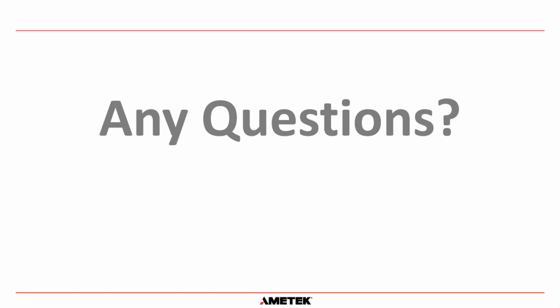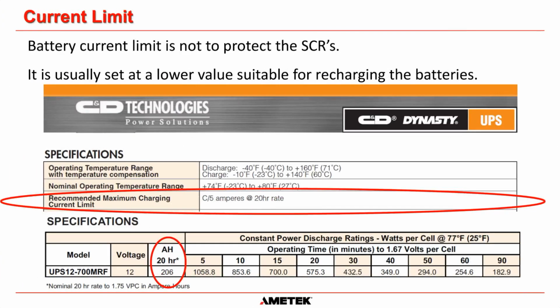Could I repeat the maximum battery charging limit? That is dependent on the battery manufacturer. You have to get that from the battery manufacturer's data sheet. For that C&D battery, it was the C rating of the battery divided by 5 at the 20-hour rate. So that's 206 divided by 5, which would be 41.5 amps for this specific battery, which is a UPS 12700 MRF. It does not apply to any other battery, only this specific model and manufacturer. Okay.